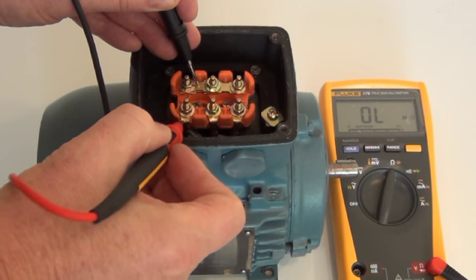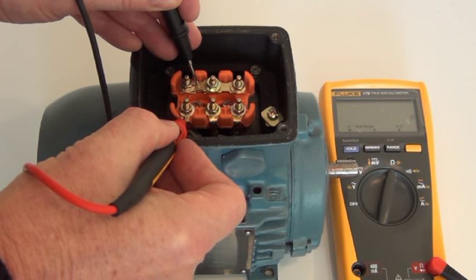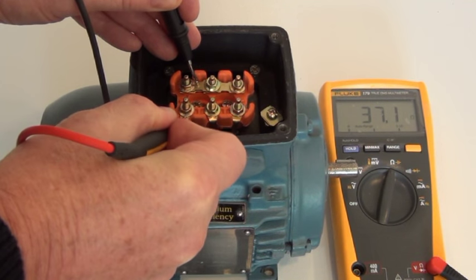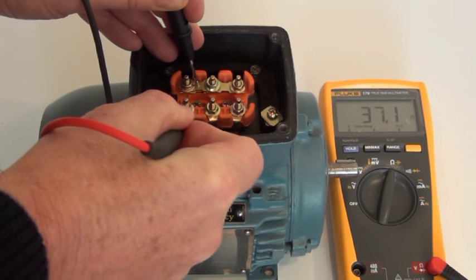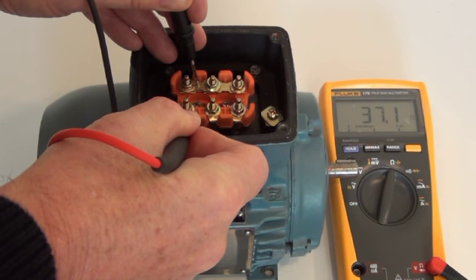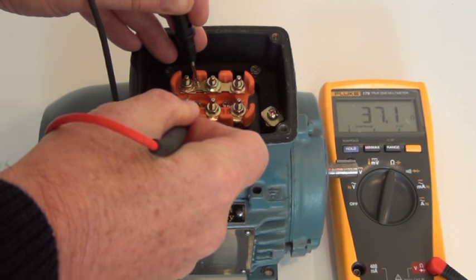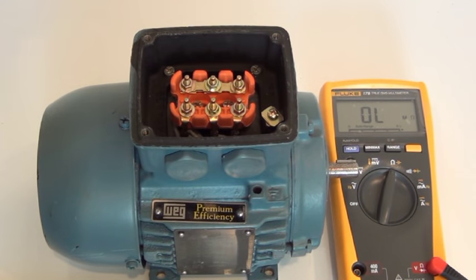Then I'll touch it onto the next terminal, which is W, and I've got 37.1 ohms. So that motor is showing that it is balanced to within 0.5 of an ohm, so that motor would function correctly.